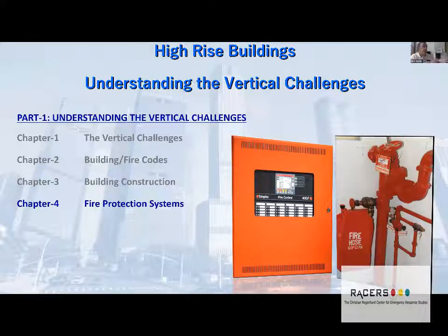Other types of extinguishing systems - we're all familiar with commercial hood systems. In high-rise buildings, when you have a cafeteria or restaurants, we all know they have an exhaust system. The big thing firefighters should look at as a best practice is to have a copy of the duct run mounted by the manual pull station in the kitchen, and also have one readily available at the fire command center. The higher up they go, they take left turns, right turns, and everything else. I think Jerry had a fire in a high rise where the ductwork came out into the subway.